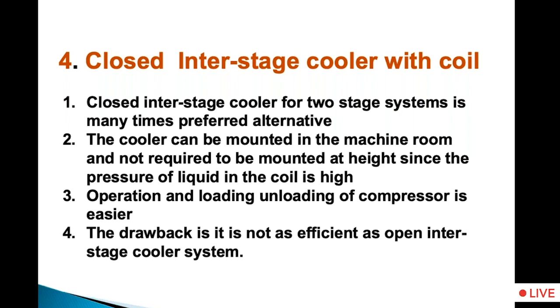You can mount the cooler inside the machine room. It need not be mounted at a height. You need not have an automatic capacity controller, which is very essential in open interstage cooler operation, to ensure that the interstage pressure does not exceed the allowable pressure. And as I mentioned, it is not as efficient as the open interstage cooler.